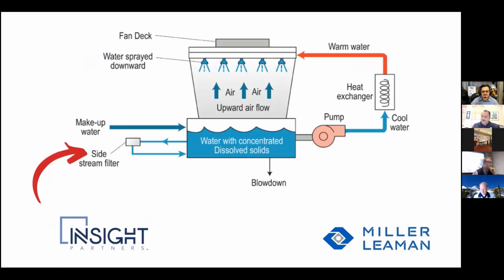Cooling tower itself. As we all know, that's the biggest air washer out there, the cooling tower, bringing the air through the tower, collects all the different contaminants, a lot of organic material, and pollen, cottonwood seed, depending what time of year it is. And then, of course, anything blowing in the air, if there's construction nearby, sand, dirt, all sorts of things. You can find birds in there. You can find a lot of different things during the season when there's a lot of bugs.